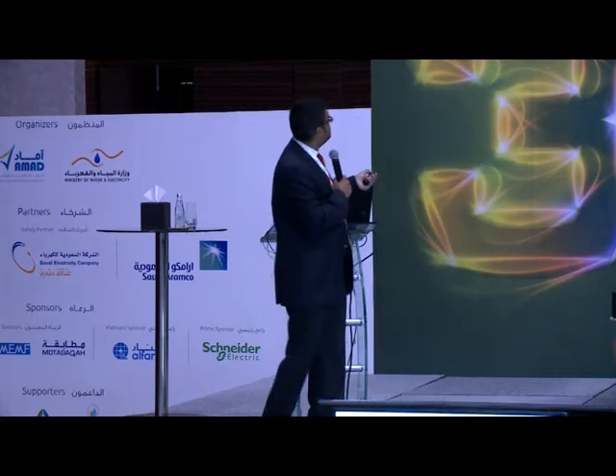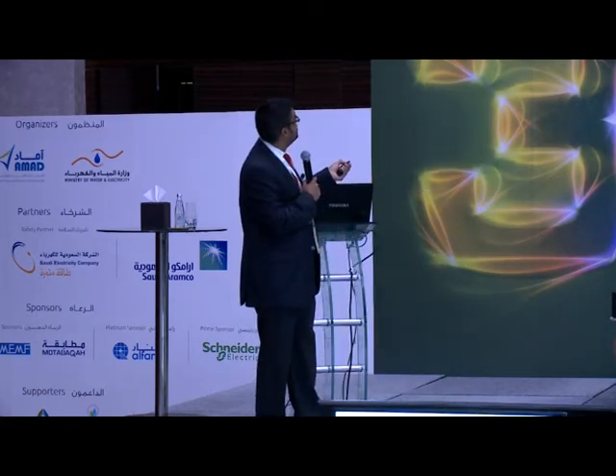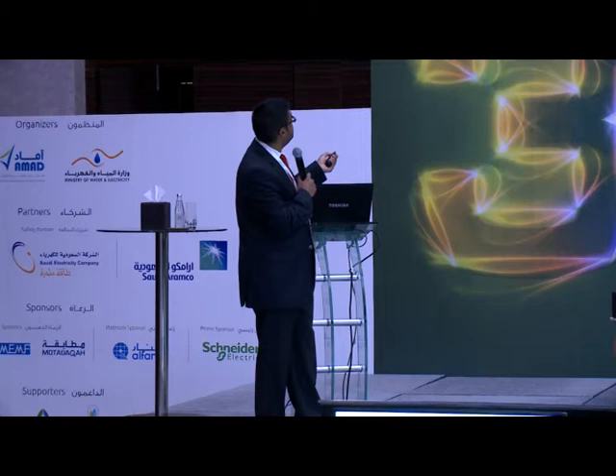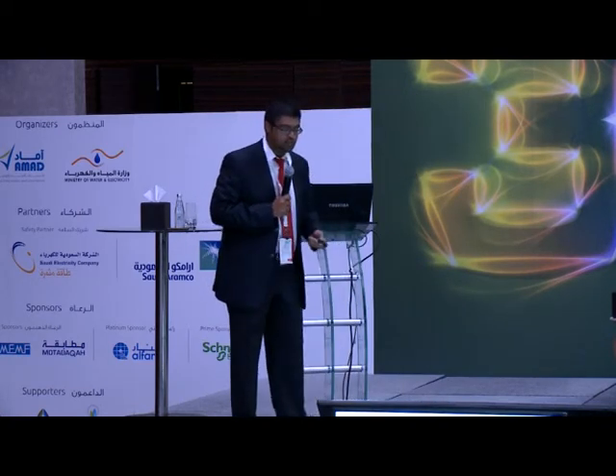My slide here is slightly outdated, so bear with me. But with regards to the shock boundary, now we only have the limited approach boundary and the restricted approach boundary. The prohibited approach boundary is done away with, and you've got your arc flash boundary. Now, please don't be deceived by my slide. You need to calculate, because your arc flash protection boundary could be within your shock boundary or outside of your shock protection boundary. This is just a drawing for demonstration purposes. So we spoke about the arc flash protection boundary.